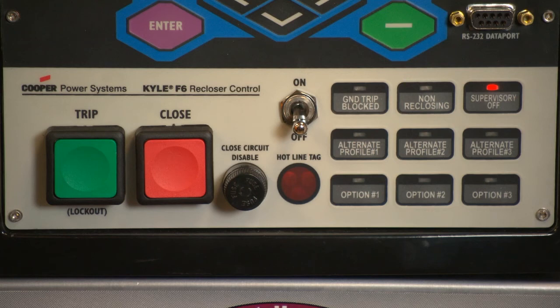Important: hotline tag is intended solely for live line work applications, such as maintenance, repairs, or improvements to the distribution system that occur while the line remains energized. Hotline tag prevents all closing attempts and shifts protection to one trip to lockout on the composite curve of the hotline tag definite time and the TCC1 curve, whichever is faster. Hotline tag takes precedence over cold load pickup, non-reclosing, and fast trips disabled.